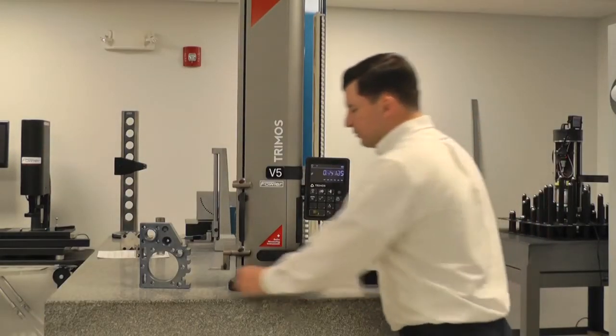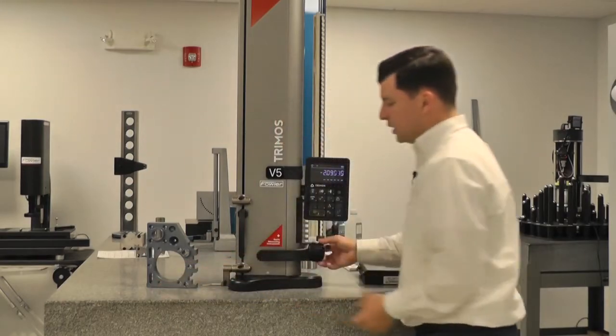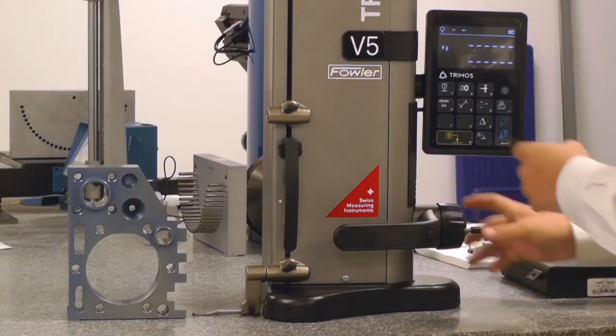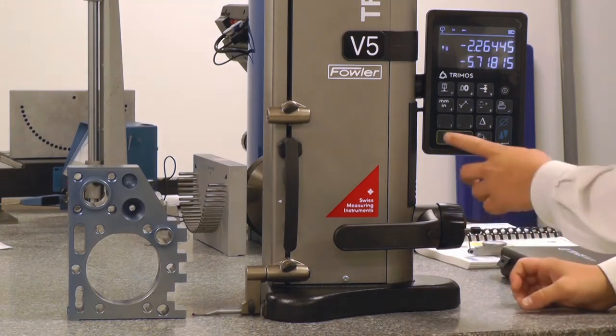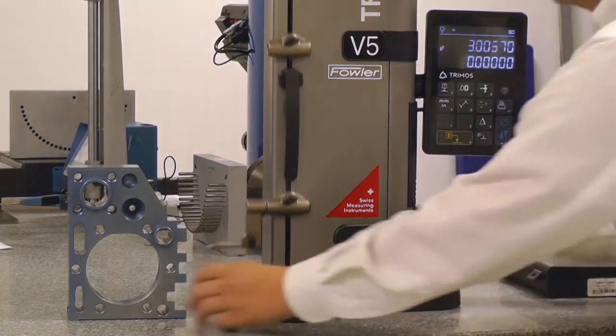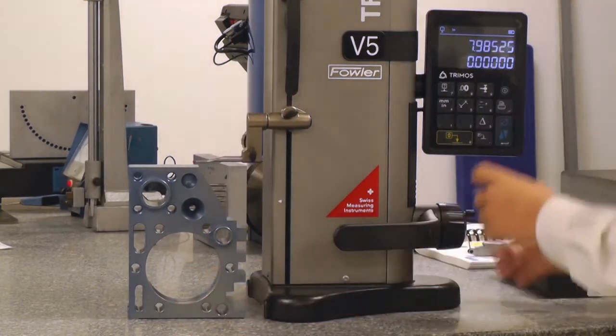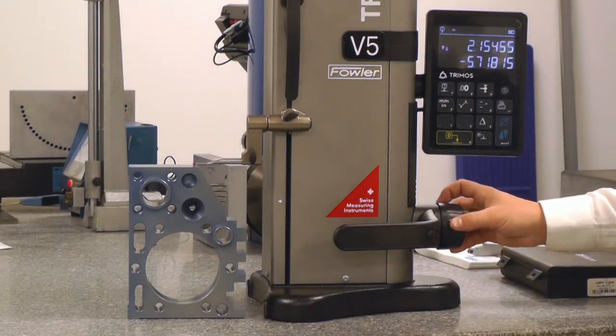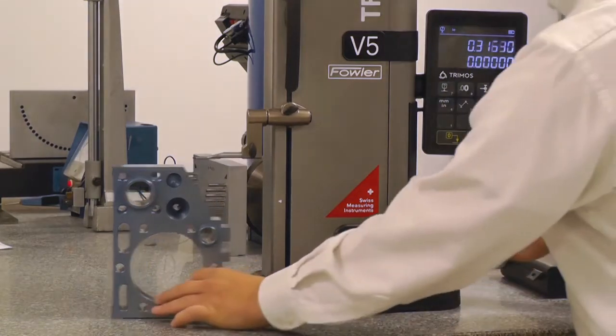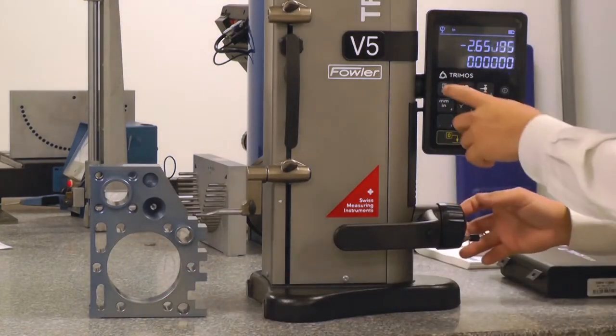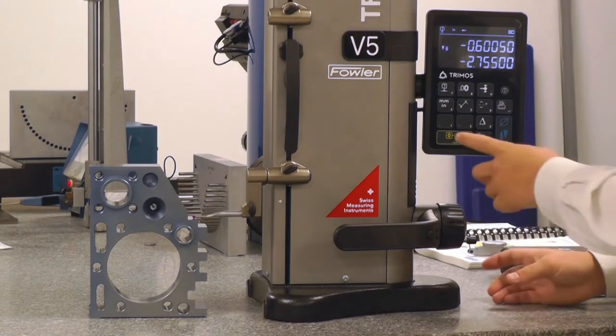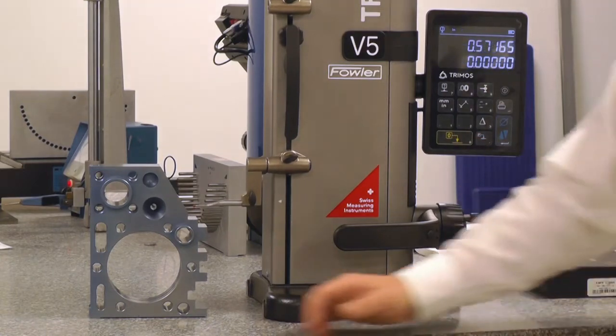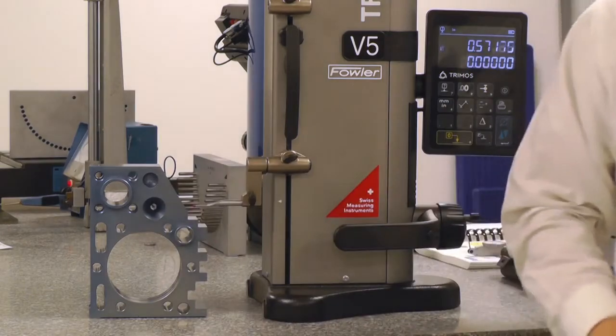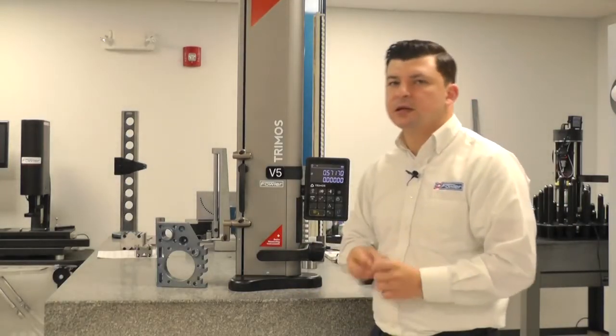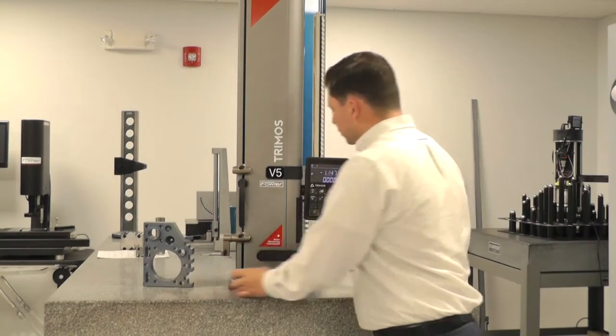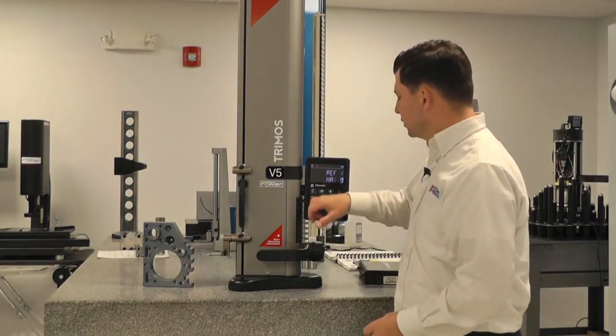If I want to establish my reference, I will come down to whatever position I want to establish a reference, say in reference 1, say 0, say in reference 2, 0 it out. Say reference 3, engage my probe, 0 it out. Now I've effectively established reference 1, reference 2, and reference 3, relative to datum A, datum B, and datum C. Those are the references, and that's how you will establish it.